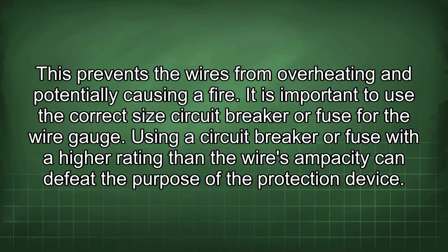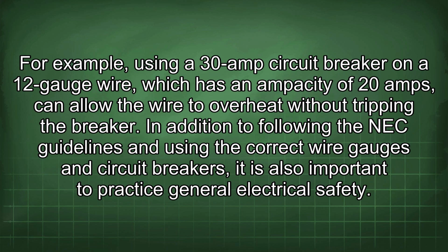It is important to use the correct size circuit breaker or fuse for the wire gauge. Using a circuit breaker or fuse with a higher rating than the wire's ampacity can defeat the purpose of the protection device. For example, using a 30-amp circuit breaker on a 12-gauge wire, which has an ampacity of 20 amps, can allow the wire to overheat without tripping the breaker.